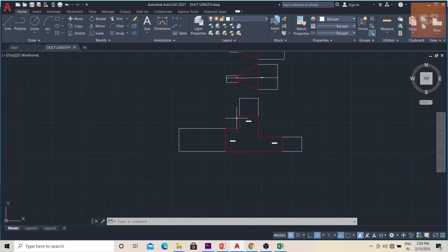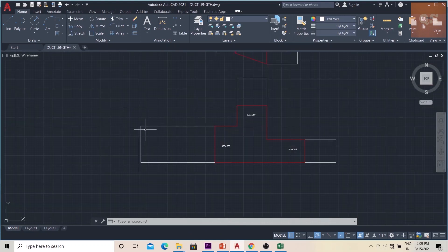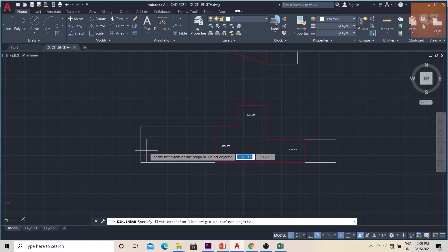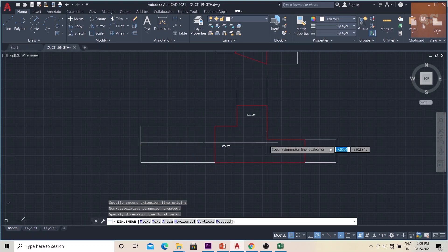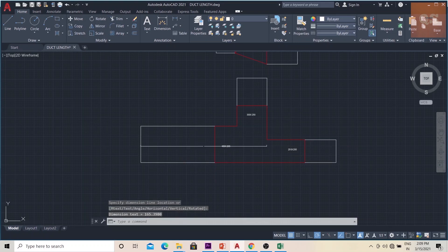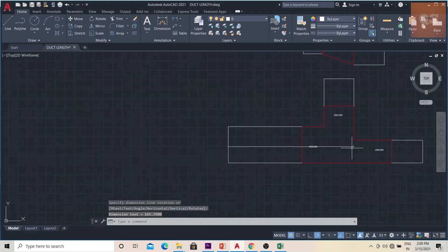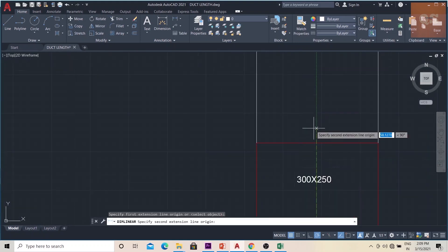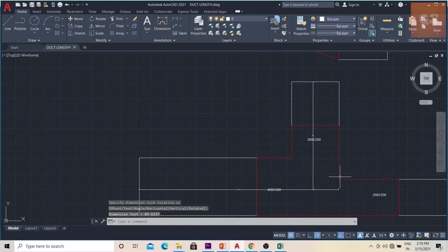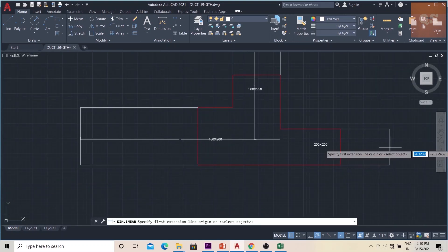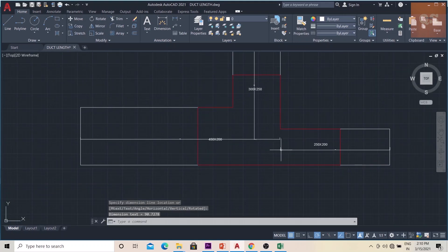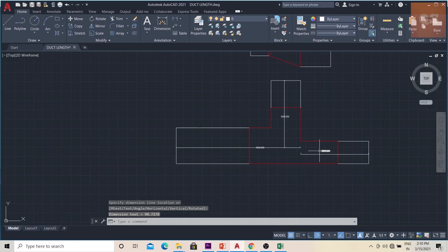Now in a T-section, you have one 450x200 coming, then it is divided into a 300x250 duct and a 250x200 duct. The 450x200 part length will be from the center part till here. The 300x250 length will be from the center part till here, and the 250x200 length will be the remaining part. This is the way you calculate the length of each part including the fittings.